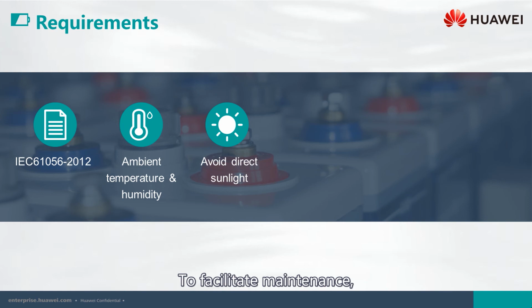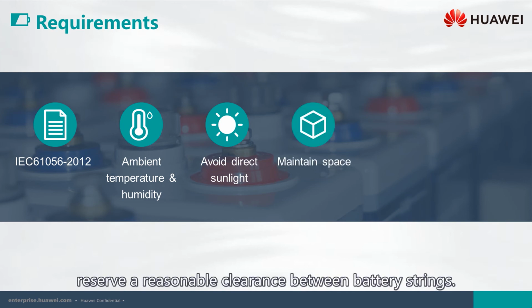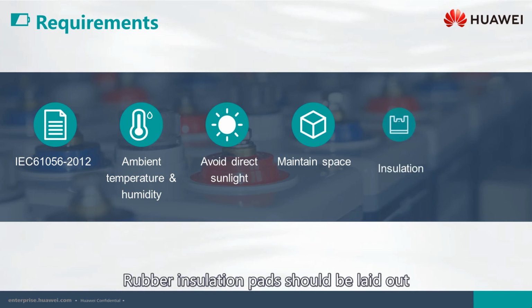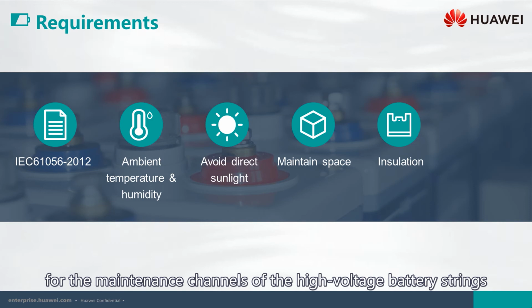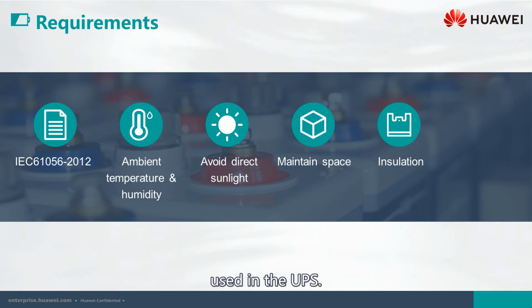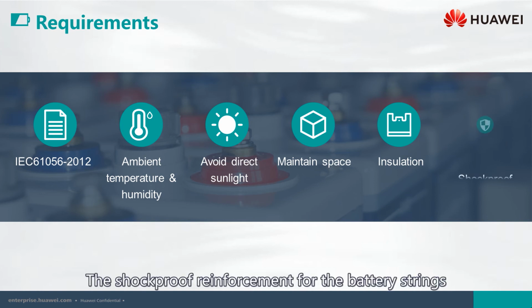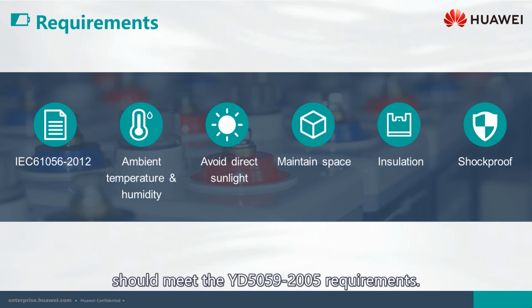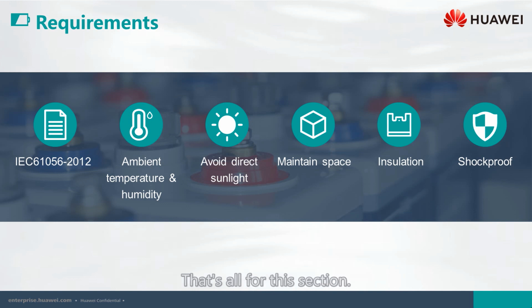To facilitate maintenance, reserve a reasonable clearance between battery strings. Rubber insulation pads should be laid out for the maintenance channels of the high-voltage battery strings used in the UPS. The shockproof reinforcement for the battery strings should meet the YD 5059-2005 requirements. That's all for this section.